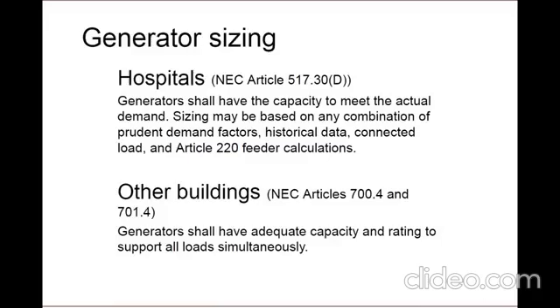Another difference is how the generator rating is determined. NEC 700 and 701 require the generator to have enough capacity to run all of the connected loads at the same time. The generator is permitted to support emergency, legally required standby, and optional standby systems. If the system design includes selective load pickup and shedding to ensure the emergency and legally required loads are fully supported, capacity reserved for the optional standby system may be deemed unnecessary.